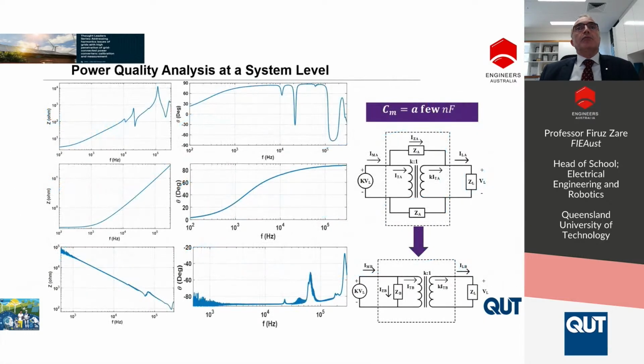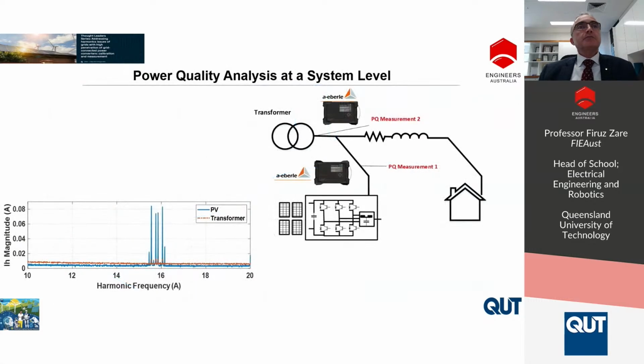We have also modeled transformers and the Miller effect of the transformer. If you can see ZA, it can be capacitive coupling between the turns of the transformer, primary and secondary, and we have analyzed that this capacitive coupling can be a few nanofarads. If you have some switching pattern coming from the distribution network or from a solar farm switching on and off, that can affect the transformer and the cable because of the LC effect of the cable and transformer, and the overshoot coming from those switching transients.